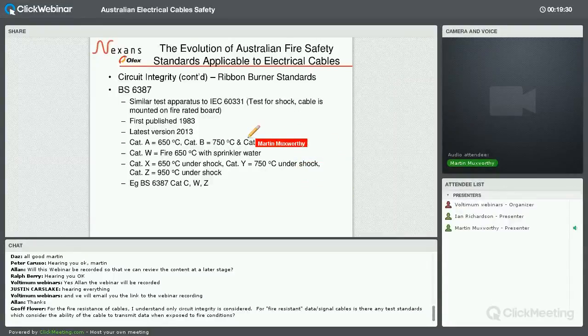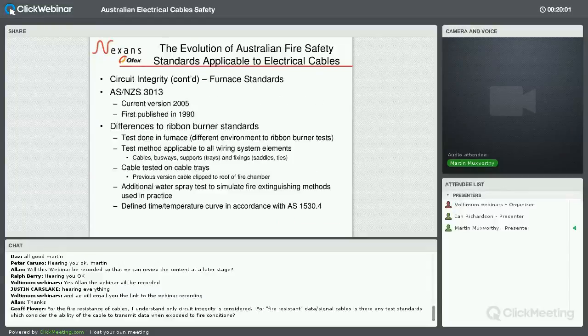The other ribbon burner test that I mentioned was a British standard, BS6387. Similar sort of test arrangement. It introduces some different category type classifications, different temperatures, 650, 750, 950 degrees. That's for fire alone. I guess the difference with this particular standard is that there's an additional water sprinkler test that you can do.